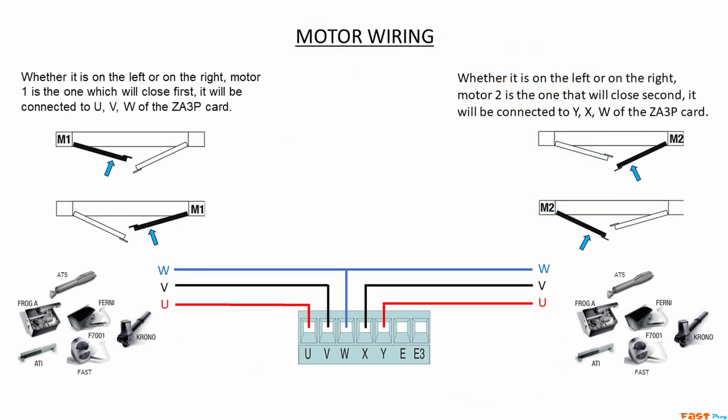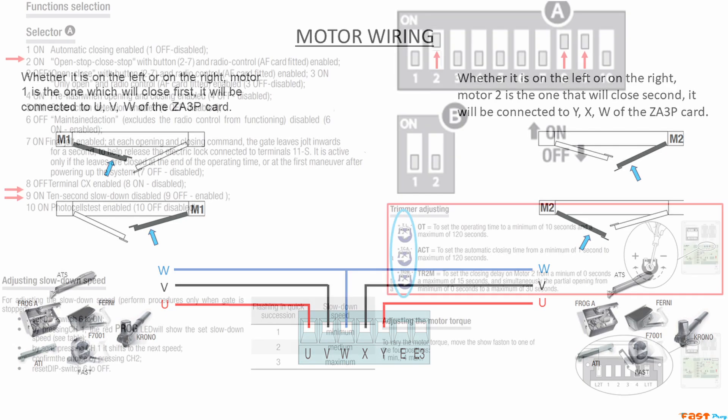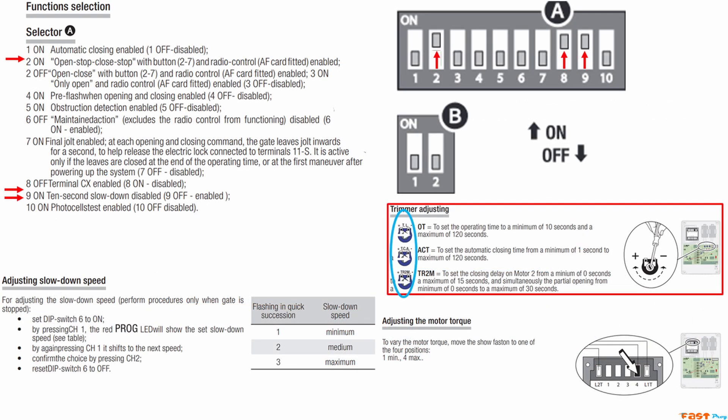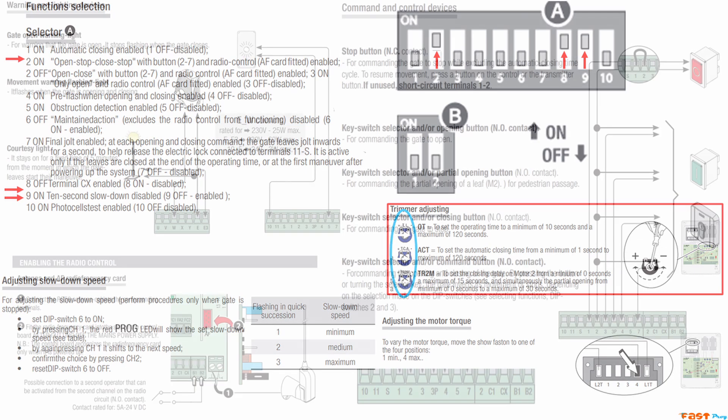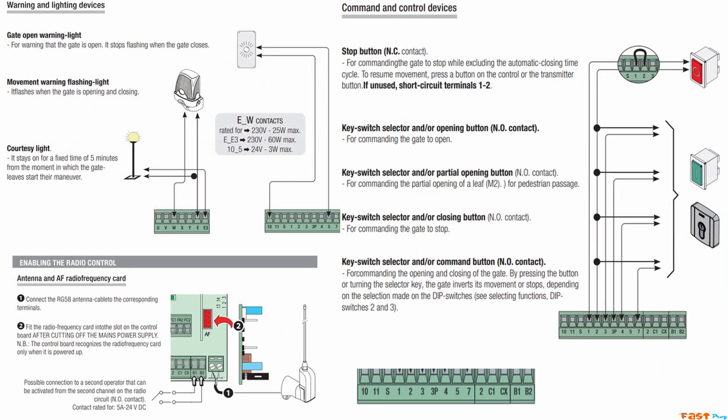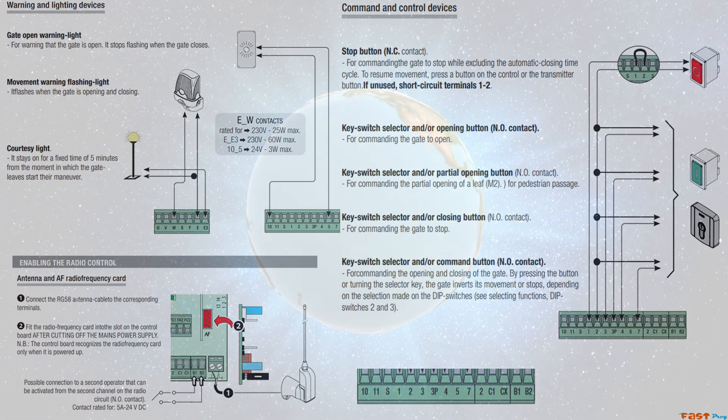If the motors don't run a full cycle or, on the contrary, run too long after reaching the stop points, adjust the OT potentiometer. A good way to check the maneuvering time is by watching the flashing light connected to the W and E terminals on the ZA3P. For reference, the light stays on for the entire operating time.